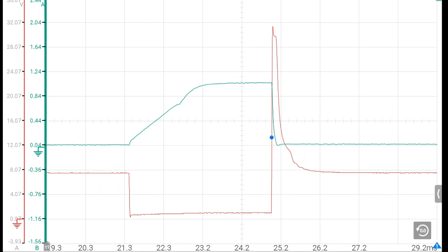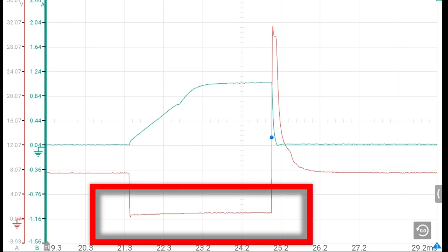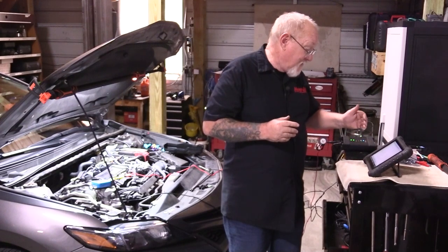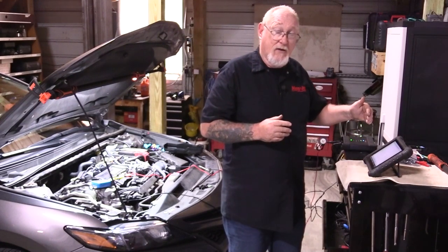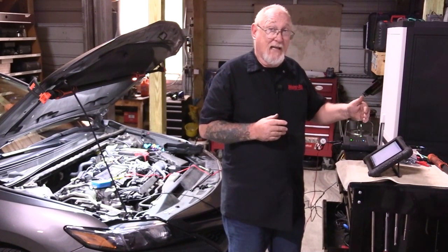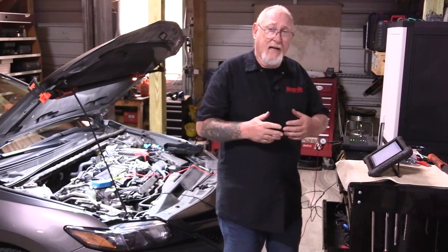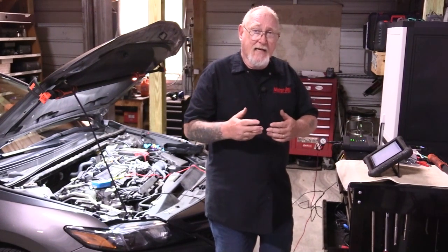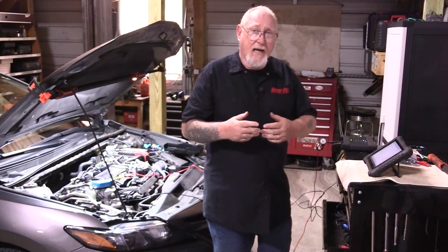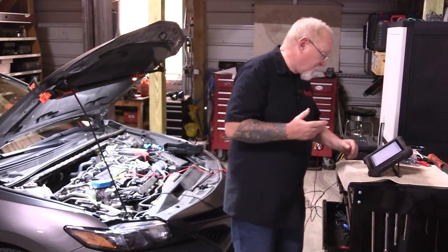Before we get to that, let me continue with what we're seeing on channel A, the voltage side. If you look very closely at that horizontal line between the start and stop, you'll see it's not perfectly flat—it's slightly curved. That's almost a mimic of the current pattern above it, and that's exactly what's causing it: the impact of the magnetic field being created as that coil becomes saturated and is turned on.